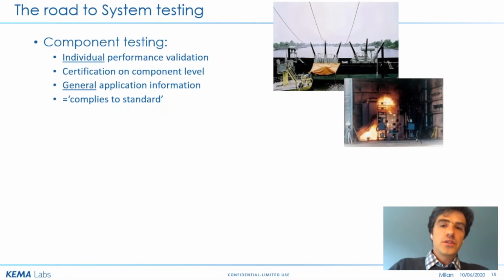That is all based on components where you have a predefined standard and a checklist on which you can do the testing and see if something complies or not. If it does, you get the label—it complies to standard. It does not mean that this component would actually fit the application, or that the intended application has been considered in the testing. And of course, if you do testing and the standards are written like that, it has to be general, which means you lose the specific aspects.